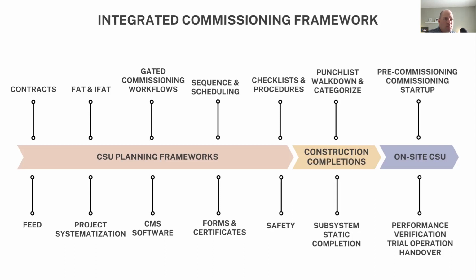So the last point I was making is static completion. It's a critical milestone, and on a lot of projects it's very vaguely defined—construction is complete, go test some stuff—and that's where things get missed. Making this much more defined in our software means clearly specifying what static completion is, because everybody's definition of done always seems to mean something different on projects. When you define your static completion exactly—what it means from a physical equipment perspective and from a documentation perspective—then everybody's clear on what that goalpost is, exactly what needs to be completed and signed off, so we can move on to commissioning knowing construction activities are complete per contract, and move on to the next stage.